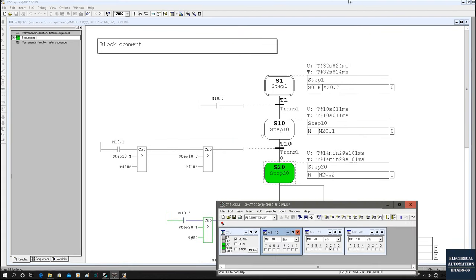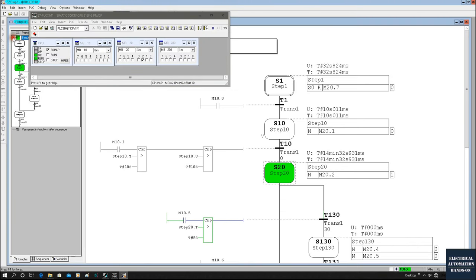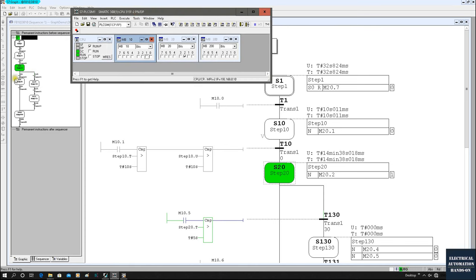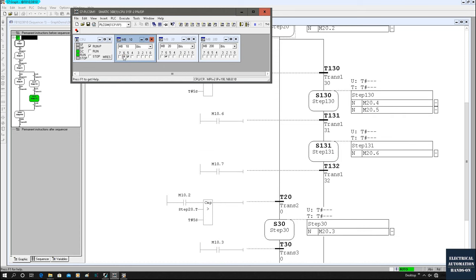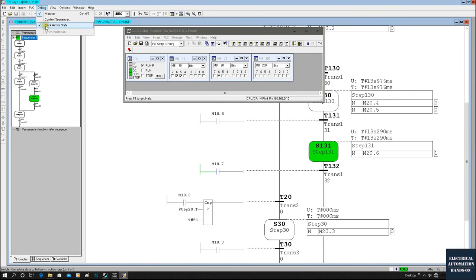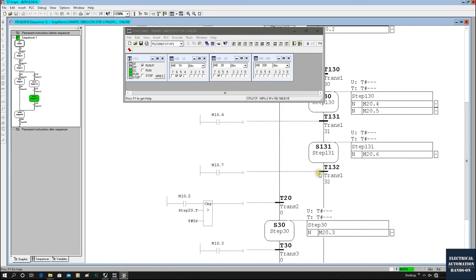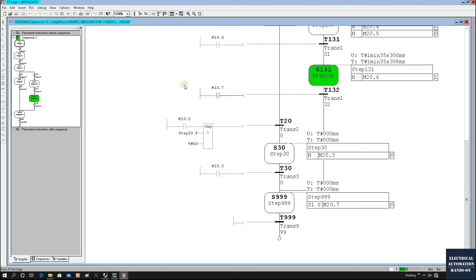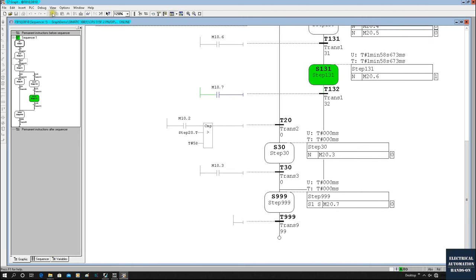Once we activate here, the system will highlight and focus on the active step. Using the simulation, I'll activate M10.5 to run into this branch — and now my window will automatically track the active step. With track active state enabled, my window will automatically track what is going on. This is very useful while doing commissioning, so your screen always tracks the active step and based on this you can troubleshoot other things.